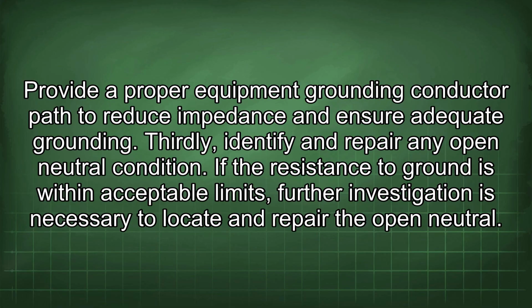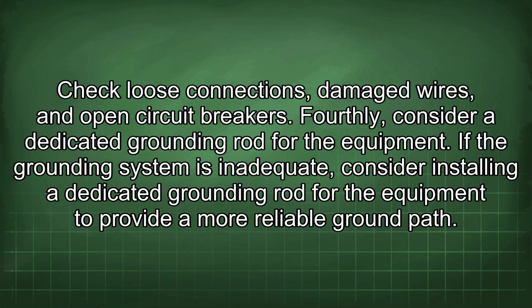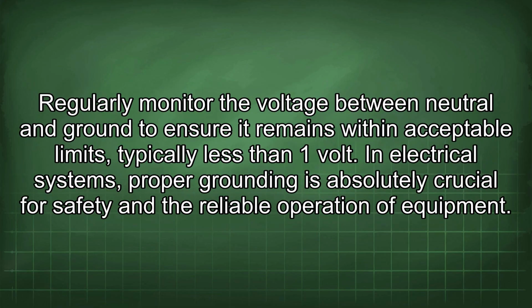Thirdly, identify and repair any open neutral condition. If the resistance to ground is within acceptable limits, further investigation is necessary to locate and repair the open neutral. Check loose connections, damaged wires, and open circuit breakers. Fourthly, consider a dedicated grounding rod for the equipment. If the grounding system is inadequate, consider installing a dedicated grounding rod for the equipment to provide a more reliable ground path. Regularly monitor the voltage between neutral and ground to ensure it remains within acceptable limits, typically less than 1 volt. In electrical systems, proper grounding is absolutely crucial for safety and the reliable operation of equipment.